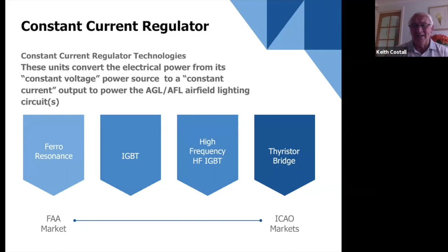I've brought up two circuit block diagrams, flow diagrams, to explain this. I've taken this diagram—and this is where we're non-aligned—from an ADB SafeGate thyristor-based MCR3 as a flow diagram, showing it as a thyristor-based unit. Basically, we have thyristors, which are units that switch. So every half cycle, they switch, switch, switch, switch.